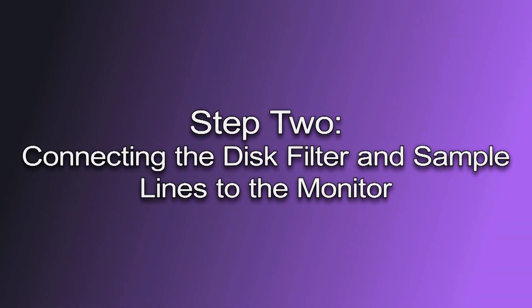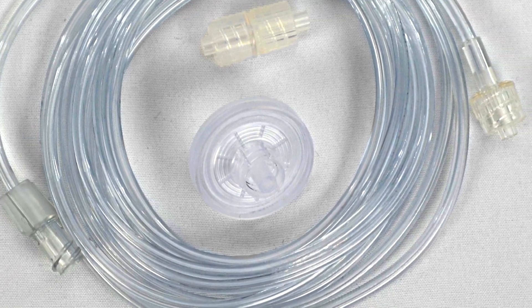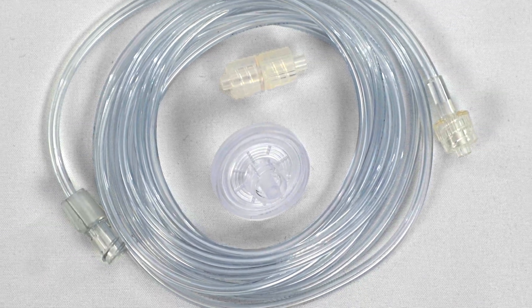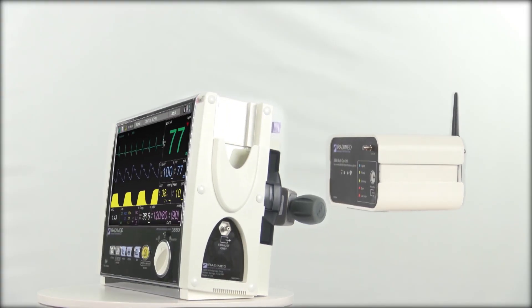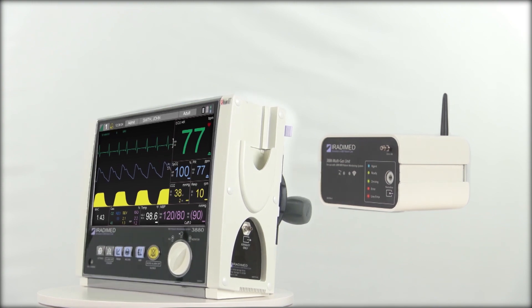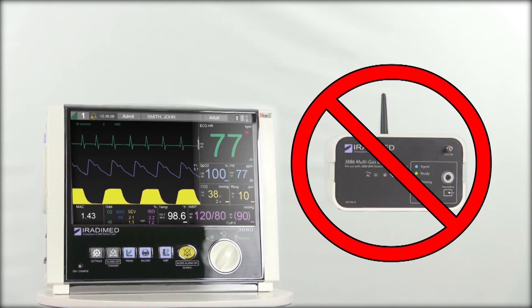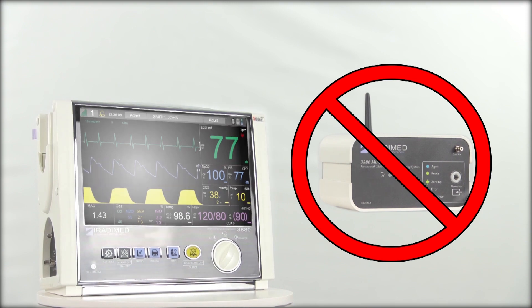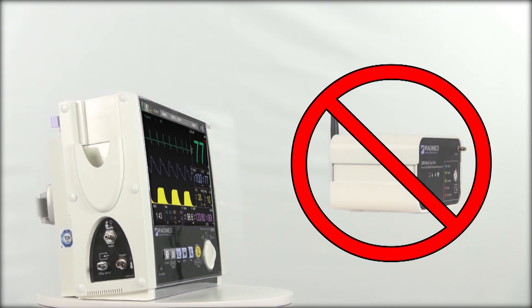Step two: connecting the disc filter and sample lines to the monitor. Each IRADIMED sample line kit includes a new hydrophobic disc filter, sample line, and adapter. The adapter may not be needed for all applications. When monitoring the end-tidal CO2 from the 3880 MRI monitor and not the wireless multi-gas unit, the user should always ensure the agent's parameter is turned off.